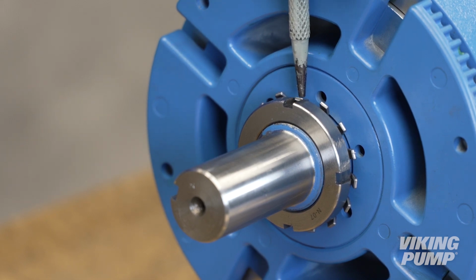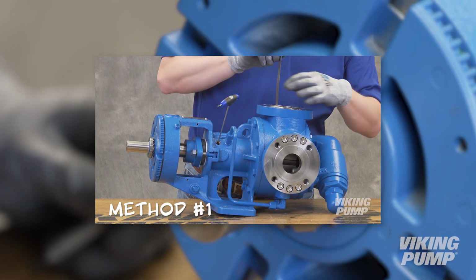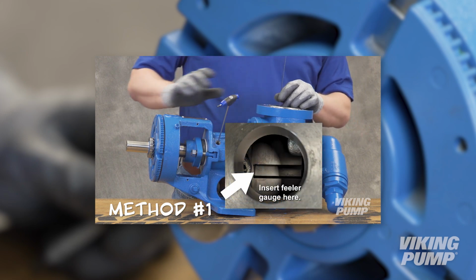Failure to tighten the lock nut or engage the lock washer tab could result in early bearing failure and cause damage to the rest of the pump. You can now set the end clearance. The end clearance setting can be found in the technical service manual. Please refer to our video, Setting End Clearance, for details on this procedure.